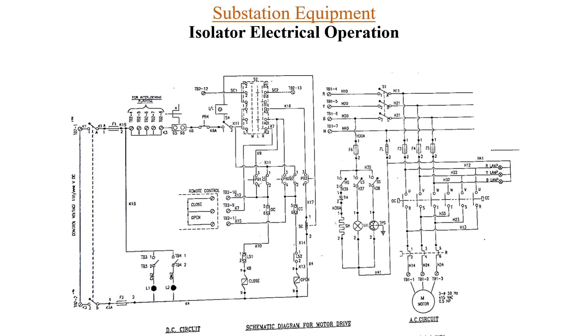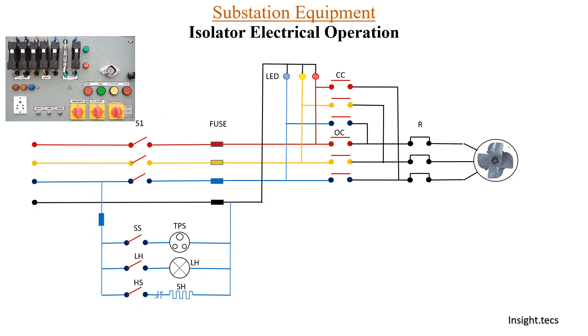The basic wiring for electrical operation is divided into two parts. The first part indicates the AC supply power circuit for the motor — you can see R, Y, and B phase. Whenever the switch is on, power comes to the motor through a contactor switch. The contactor switch is operated using a DC circuit at 110 volts. We will now discuss in detail the power circuit and how the contactors are operated using this DC circuit.